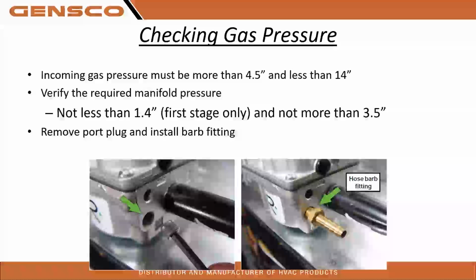And not more than 3.5 or 3.2, depending on the models. Okay. So you're going to remove a port plug and install that barb fitting to be able to access that. This is an open burner style, so you do not have to reference the burner. If it was a sealed combustion unit, like a 90%er would be, then we're going to have to reference the burner port to actually get true values there. So we'll show some pictures of that as well.